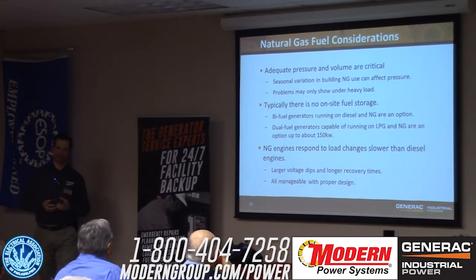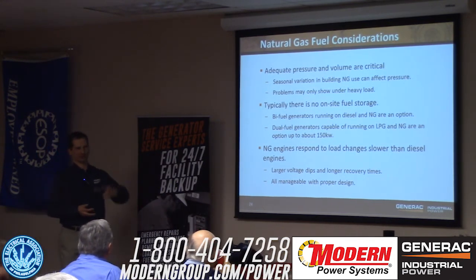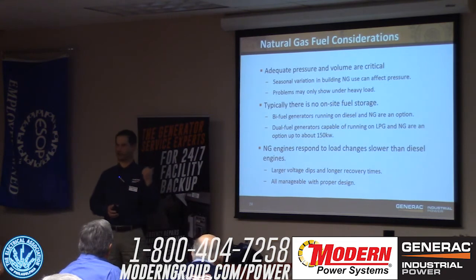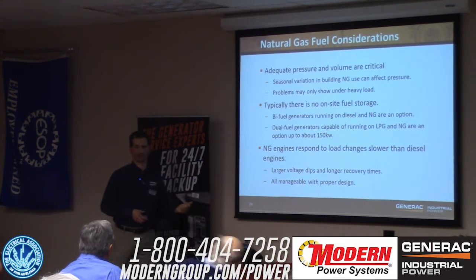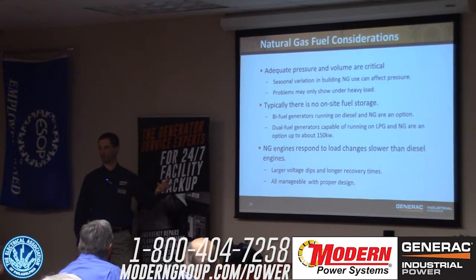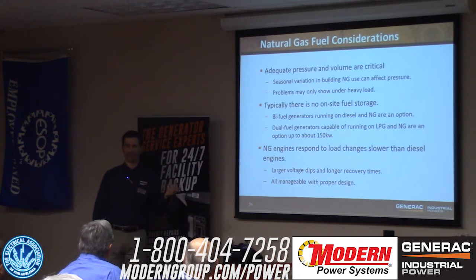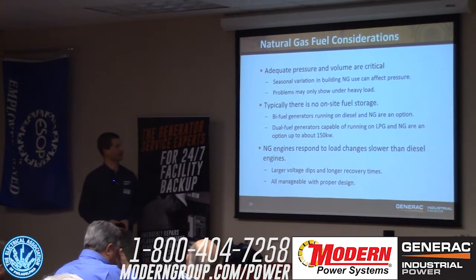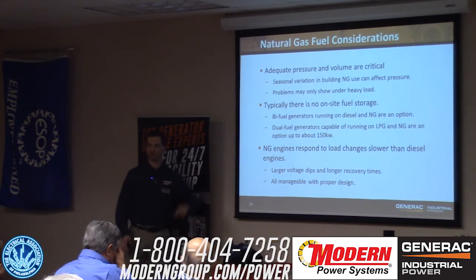You've got to have pressure and volume. As I said to the guys before we started, we are not hooking up a barbecue grill here, folks - these things have an appetite. A 500 kW genset, for example, is going to look for about 5,800 cubic feet an hour. If you don't pipe that properly, the thing is going to fall on its face when they go load bank it. You may have seasonal variation in that gas pressure out on the street.